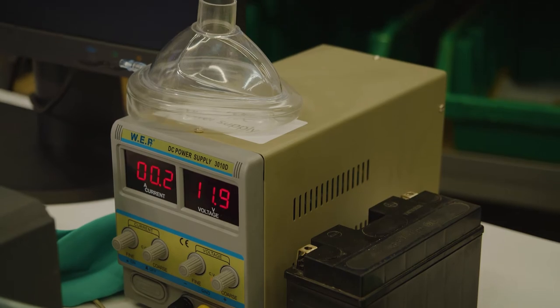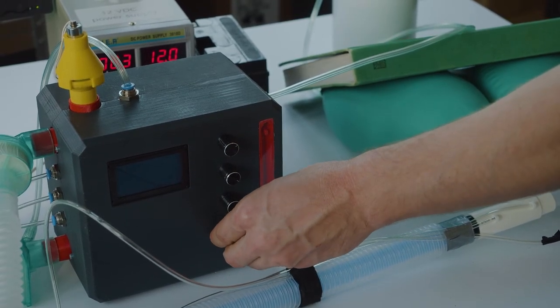We are also working on additional features. As soon as we finish the ventilation part, we'll start focusing mostly on oxygen concentration, so that you remain fully independent from whatever infrastructure might be there. The aim is to be very flexible about power sources, to have backup batteries, to let you build hospitals in whatever environment you have, with whatever resources you have. We also aim to provide doctors and nurses with help in diagnosing patients — diagnosing the rhythm of breathing, the tidal volume, also in the long term — to help those people when resources are limited.